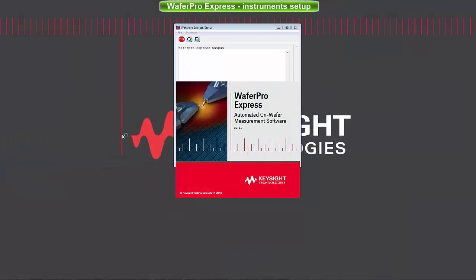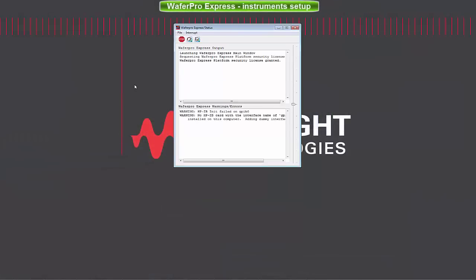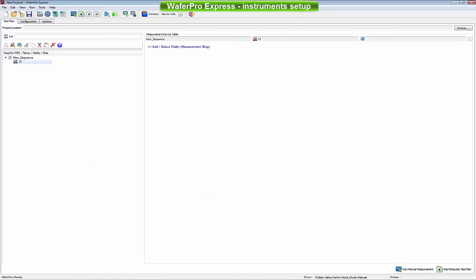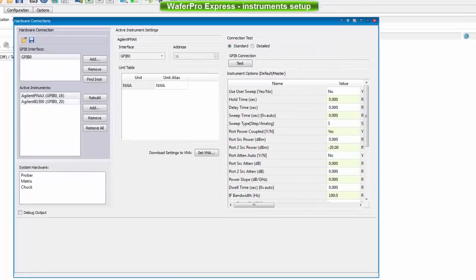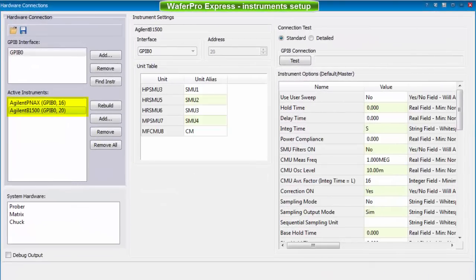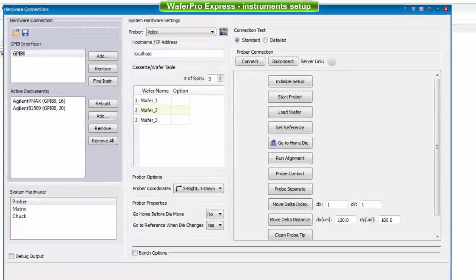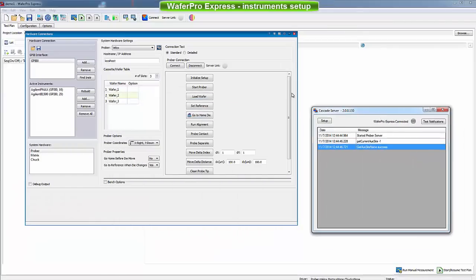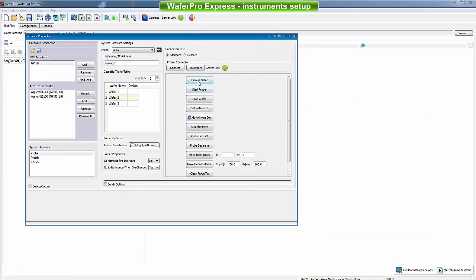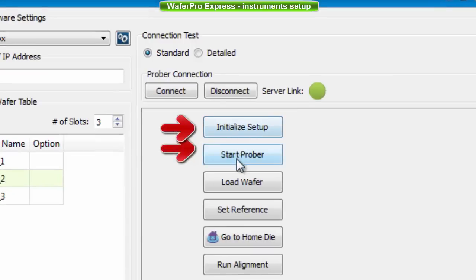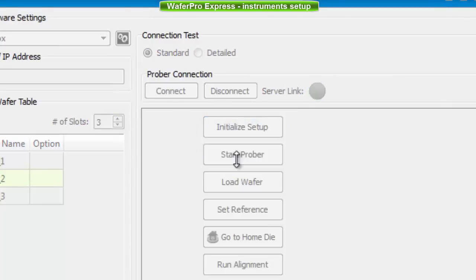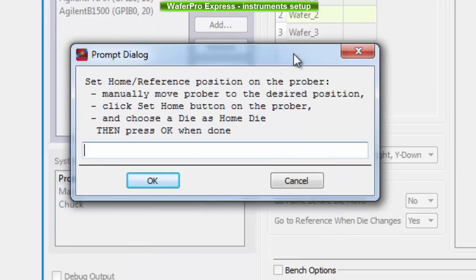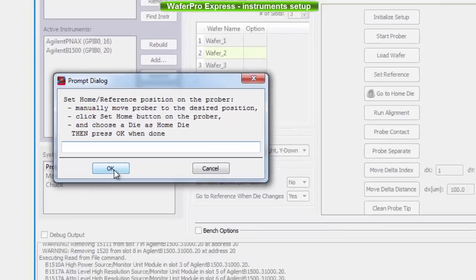After successful calibration and wafer alignment, Keysight WaferPro Express is now ready to take control of the equipment. Instruments and their options are set up in the hardware connection window. The PNAX and the B1500A are selected as instruments, while Velox is selected as Prober Controller. Velox and WaferPro Express communicate through a dedicated server. The green light indicates the connection is active. Clicking on the Initialize Setup and Start Prober buttons initializes the connection and sets the reference position to the current chuck location. A dialog asks the user to confirm that the chuck is indeed at reference.